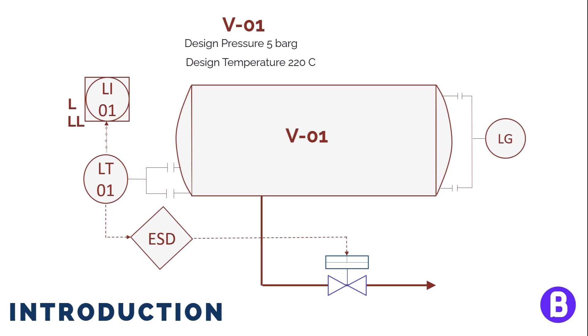If there is a pressure safety valve on the vessel, which shall send the relief load, or the load resulting from overpressure to the flare, then its main data is expected to be shown, such as the size of input and output PSV nozzles, the PSV orifice designation, which represents the PSV orifice area, so that we can know the expected capacity a PSV shall handle.